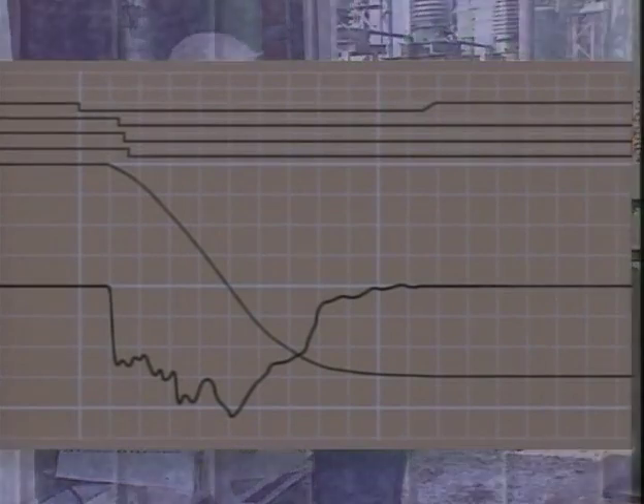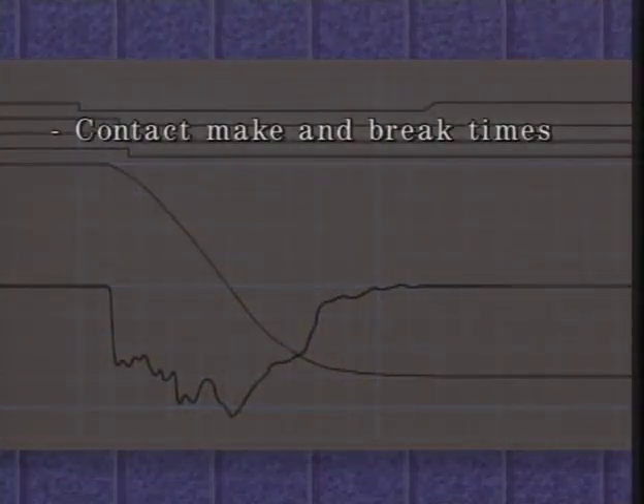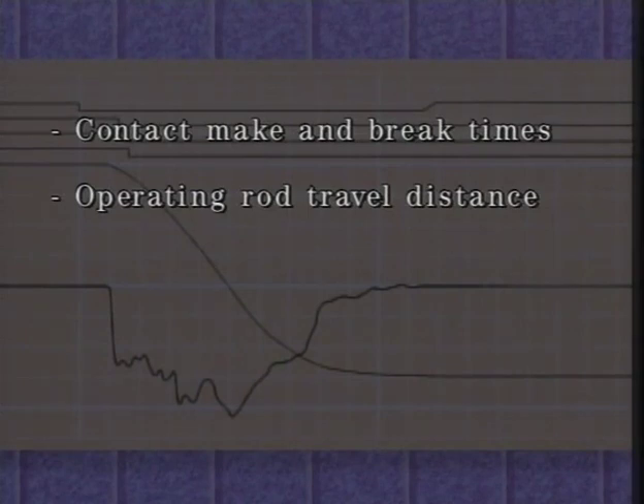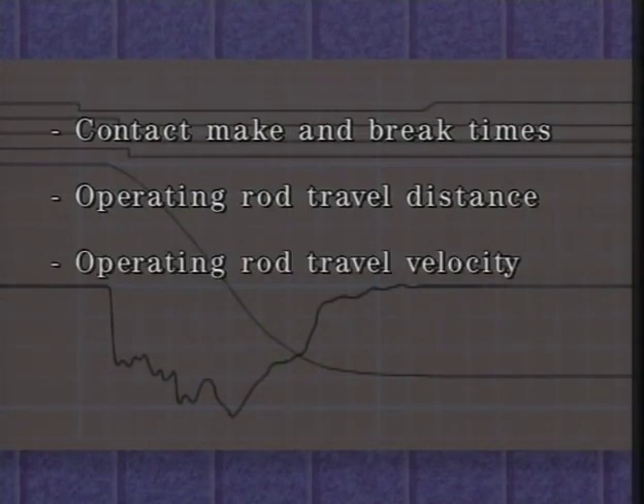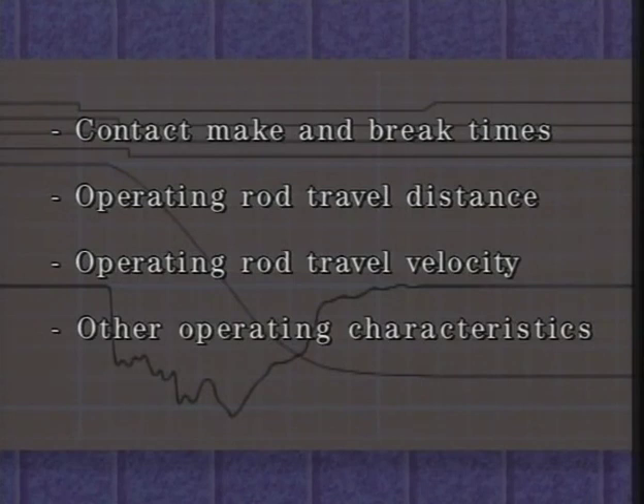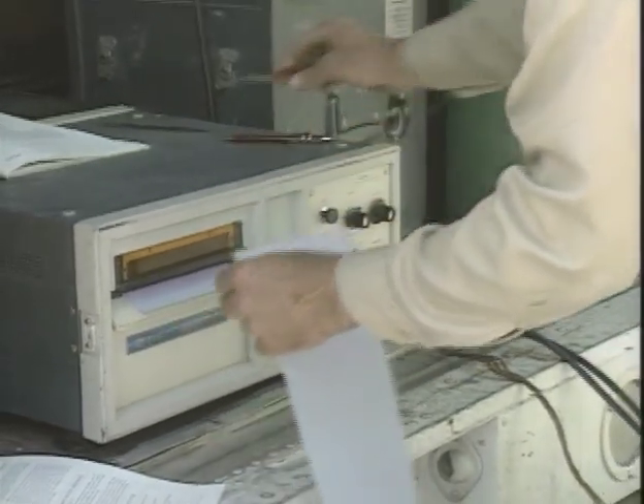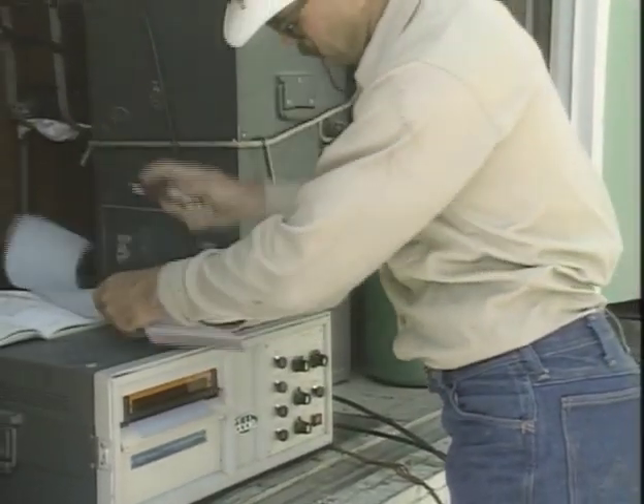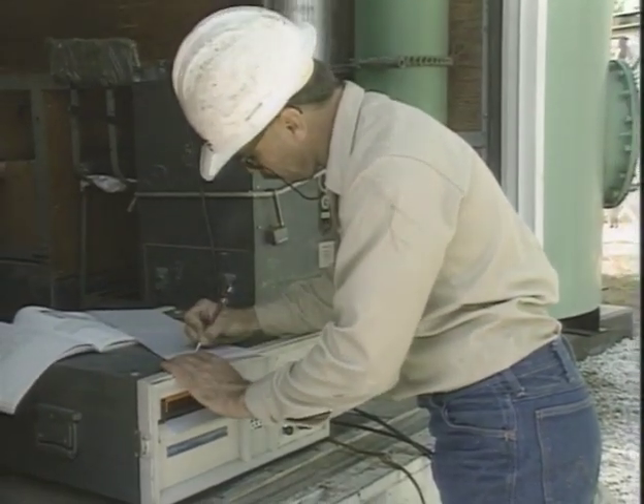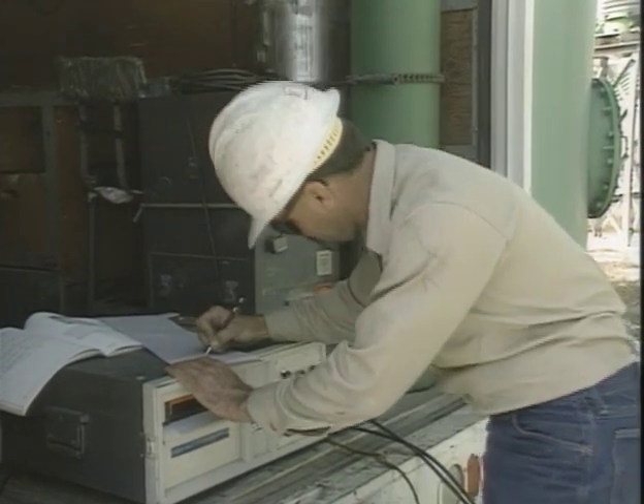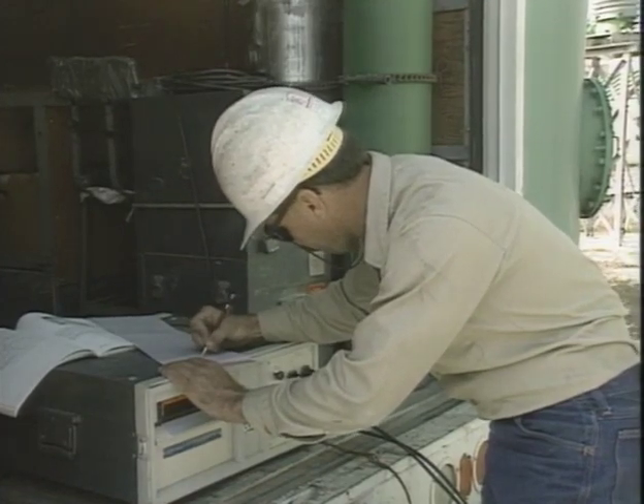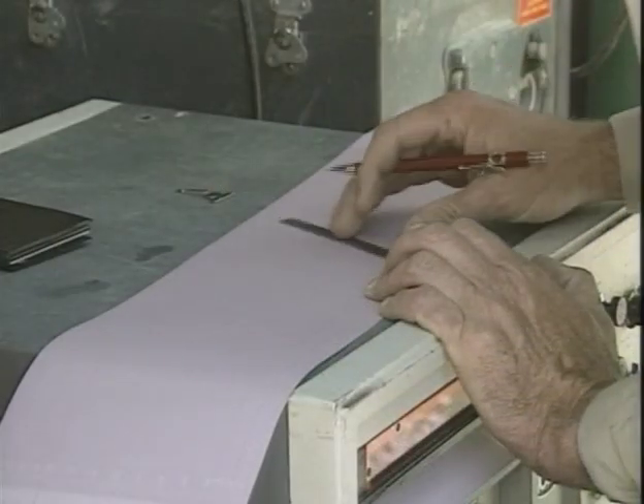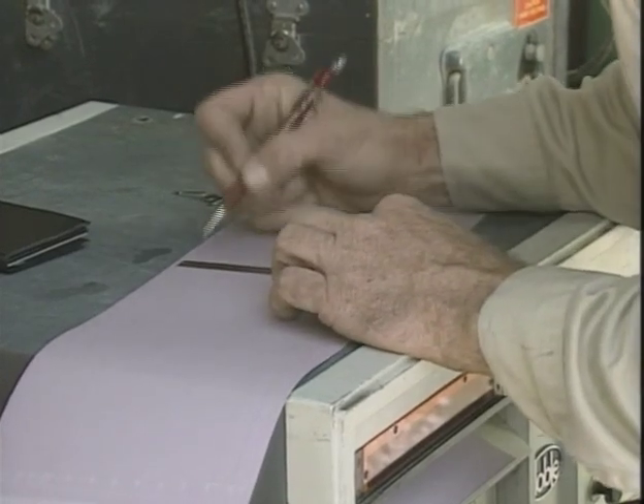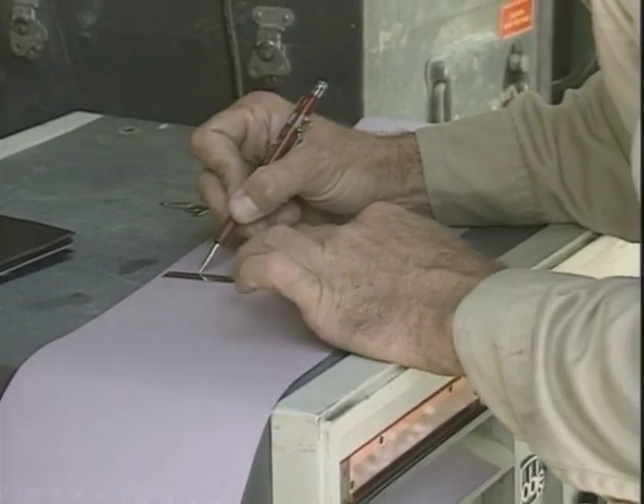These traces provide a good deal of information about the operation of the breaker, including contact make and break times, operating rod travel distance, operating rod travel velocity, and a variety of other circuit breaker operating characteristics. The time travel test is typically performed for several types of breaker operations. The traces for each operation can be analyzed to determine how the breaker is performing in comparison with the manufacturer's specifications. If the breaker's performance doesn't fall within acceptable ranges, the breaker will need to be properly adjusted before it can be put in service.